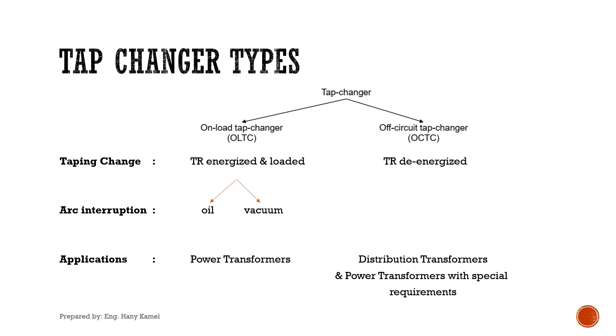On the other side, the off-circuit tap changer cannot do the same, so the transformer must be de-energized. In the OLTC, if the arc interruption medium is oil, this type is called oil tap changer; but if the interruption medium is vacuum, it is called vacuum tap changer. The OLTC is mostly used in power transformers, and with special customer requirements, an additional OCTC will be used also, but OCTC is mostly used in distribution transformers.